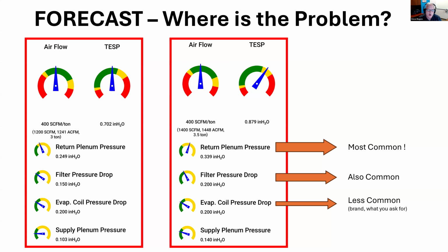So you need to do your homework and find out, oh, there's 3 different models here. If I want to not have a restrictive indoor coil, I need to order the one that's physically bigger. And that's usually what makes the pressure loss lower, it's physically bigger. Maybe it's an N coil instead of an A coil. Maybe it's an A coil that's taller, so there's more surface for the air to go through. So that's what we see for evaporator coils.